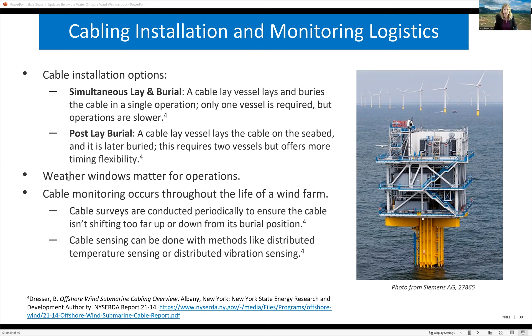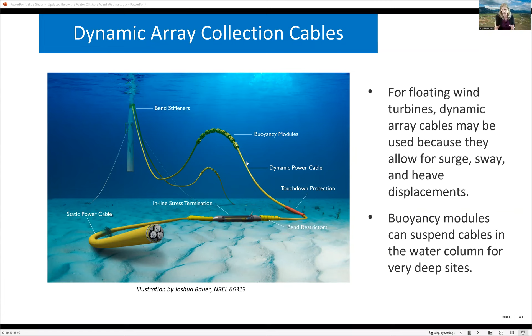As I was mentioning a little bit earlier, for floating wind systems, that array cable will be moving around as the wind turbine moves around. So there's also a lot of work that needs to go into understanding that combined design approach to that array cable for a floating wind system and the mooring line system, so that those two can complement one another. And the way they try to minimize some of this motion is they do use things like buoyancy modules and bend stiffeners to try to make sure that that power cable isn't moving too much.